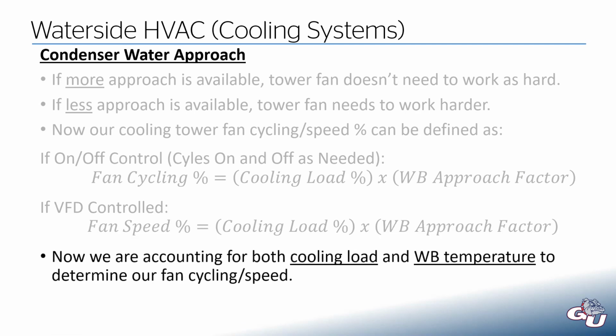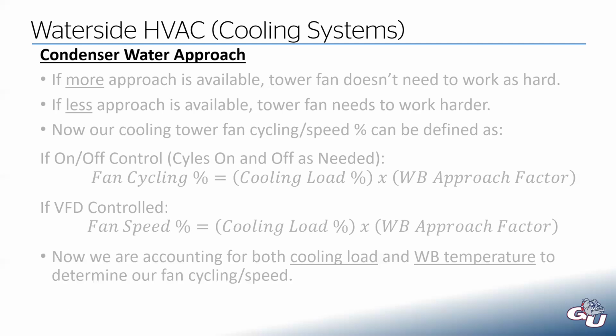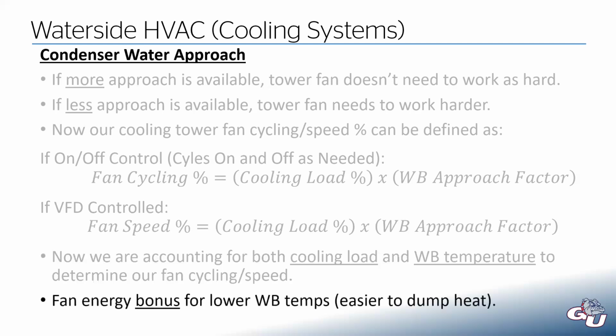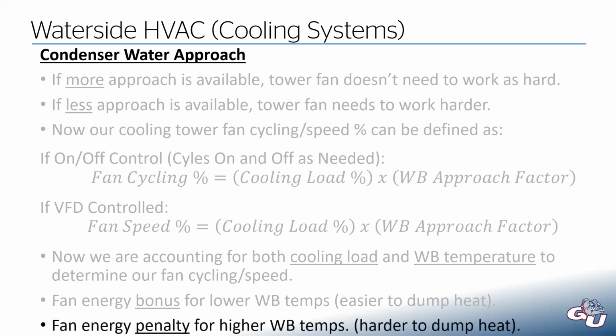With these equations, now we can account for both the cooling load and the wet bulb temperature to determine how often our fan is cycling or what speed percent we need to run the fan at. So now we have both variables that we can use. So we can scale our fan energy with our cooling load, and we can scale it with our wet bulb temperature. So we'll get a fan energy bonus for those lower wet bulb temps and a penalty for the higher wet bulb temps.